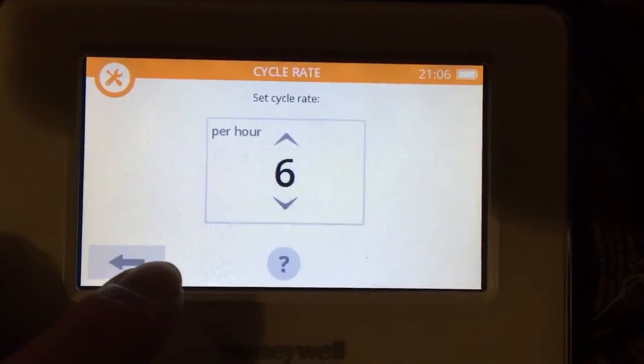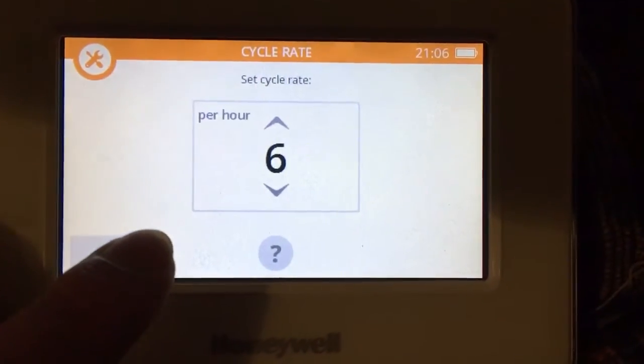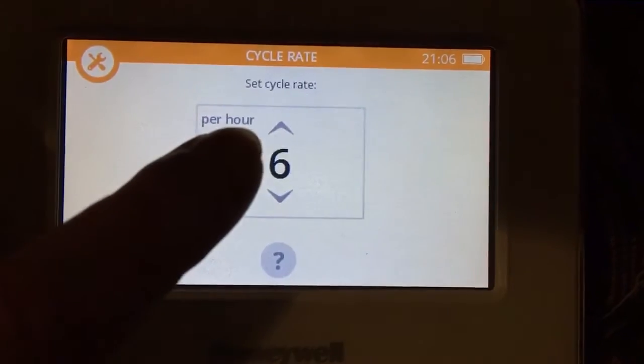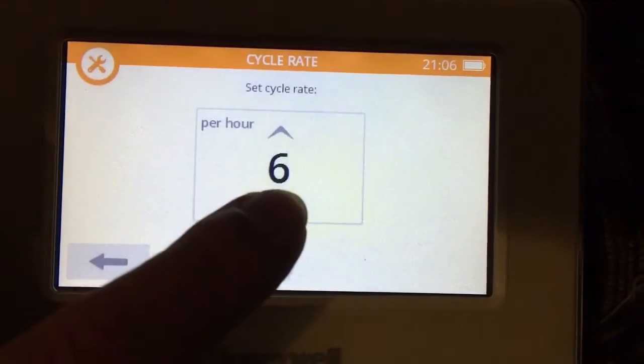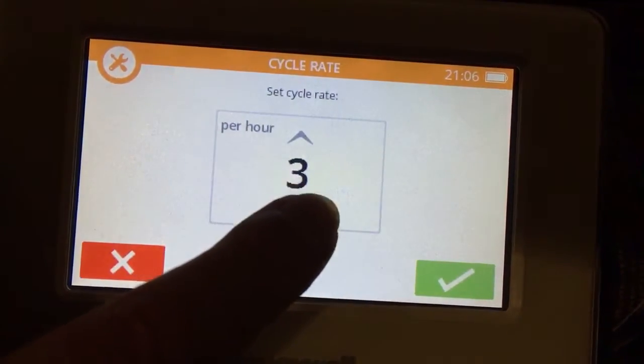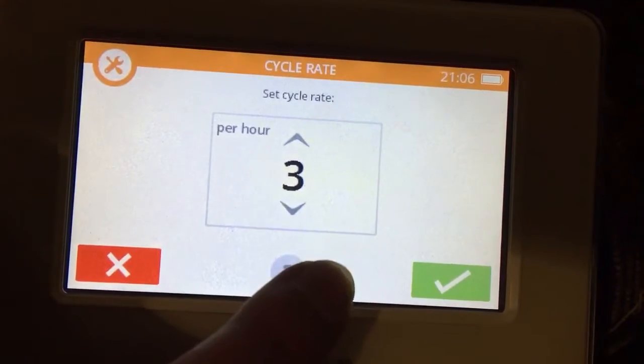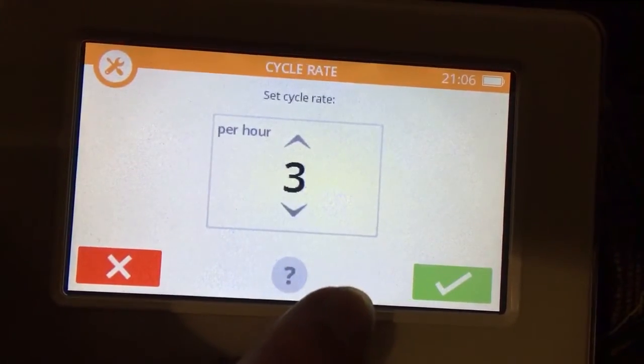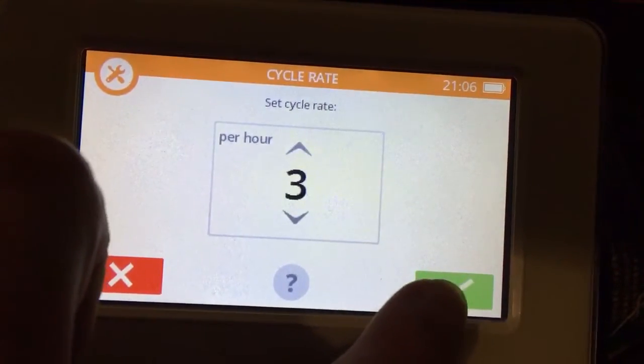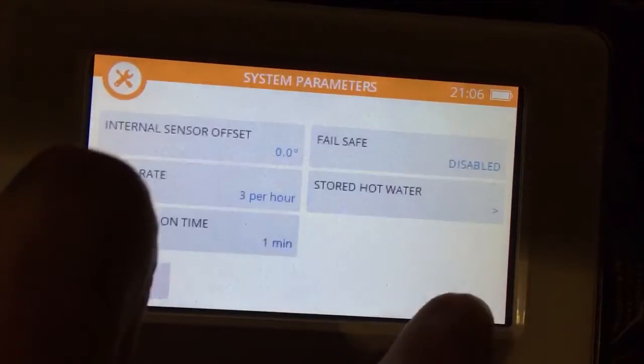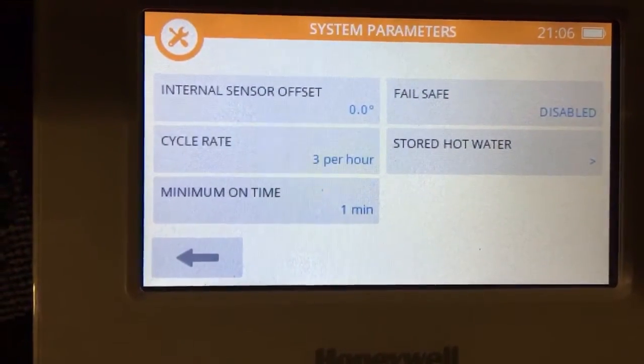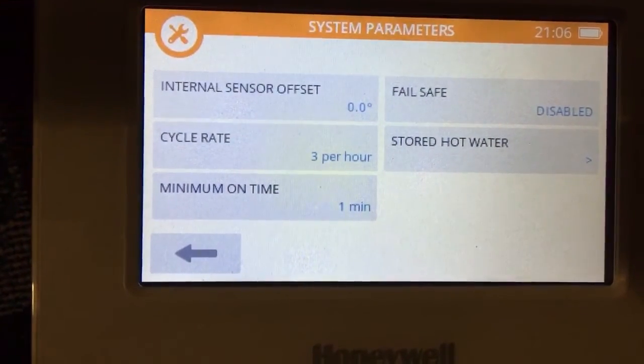So we're going to make a change here. At the moment it's set at 6 cycles an hour. For an oil boiler we're going to reduce that down to 3. And to accept you press the tick. So it's now changed from 6 cycles an hour to 3.